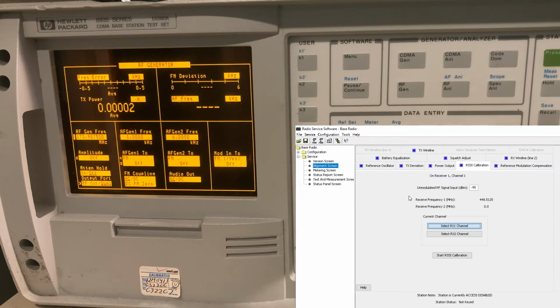So I'm going to go ahead and set up the RF generator on the service monitor to output a signal at 446.5125 megahertz and at an output power of negative 90 dBm. We go down to amplitude, type in negative 90 dBm, and that's all there is to it. We'll hit start RSSI calibration and let the station do what it needs to do.